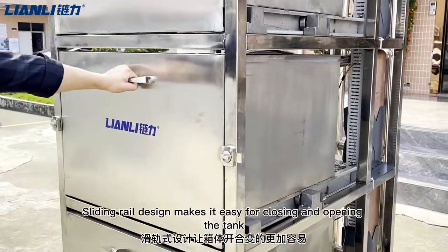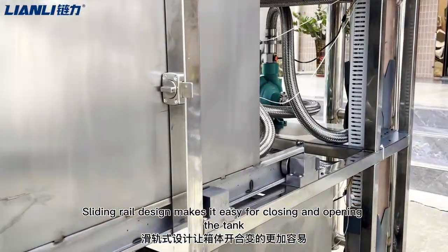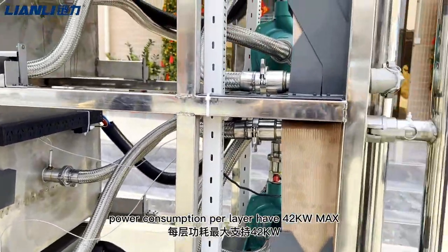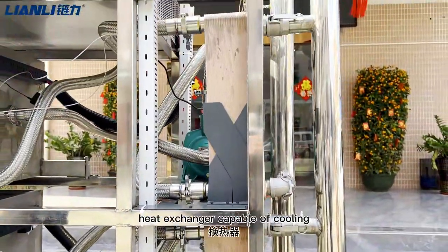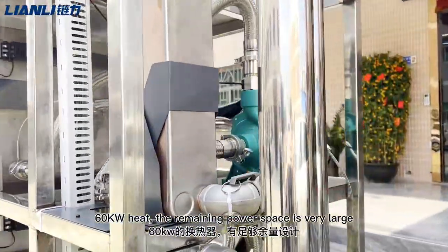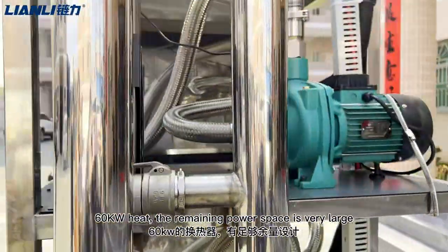A sliding rail design makes opening and closing the tank easier. Power consumption per layer is rated at 42kW max, and we have installed a heat exchanger capable of cooling 60kW of heat. The remaining power headroom is very large.